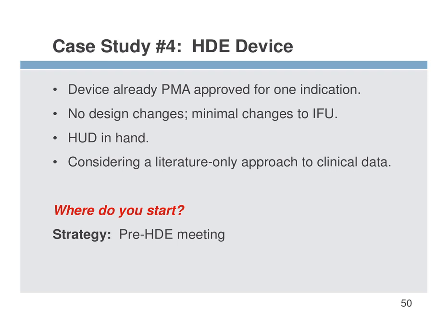You want to figure out what you want and go for it. And then let FDA say, no, you can't do that. And now you've got a conversation. Well, if we have this as our indication, does that eliminate that as a testing requirement? Yeah, I'd go for what you really, really want, and try to make the argument about why it's not a PMA, I guess, in this case.